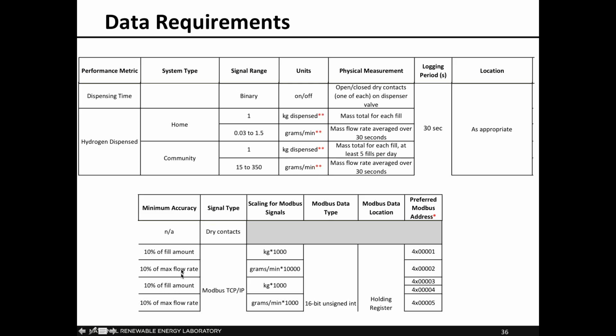The accuracy requirement for these is pretty broad, just because of the state of sensor technology today. It doesn't easily allow for a high-accuracy measurement, so we've broadened that category to make sure people can meet it. That is a non-isolated signal that will come to us over Modbus. And I have some suggested scalings here that will allow the data to come across as an integer, but then we can still retain some floating point precision. And then preferred Modbus addresses here.